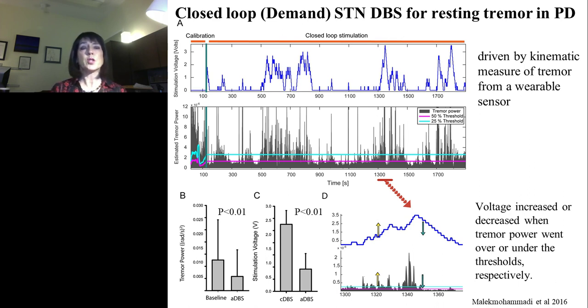What you can see from these two upper panels is the voltage is represented by the blue lines, and the tremor intensity on the lower panel is represented by the black lines. As the tremor increases above the blue line, you can see the voltage increases, and the system responded very nicely to tremor intensity. In the insert, shown by the red dashed arrow, you see a blown up time window of how we increased voltage and how we ramped it up, and how we ramp it back down at half the rate that we ramp it back up to avoid tremor rebound.